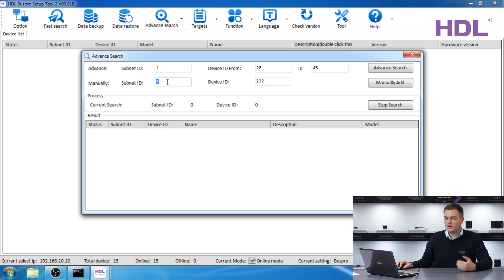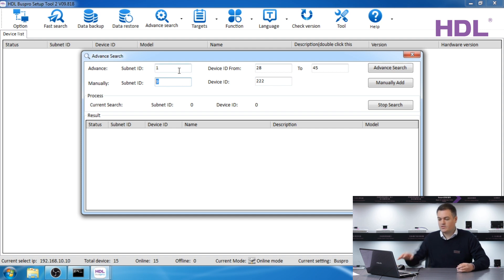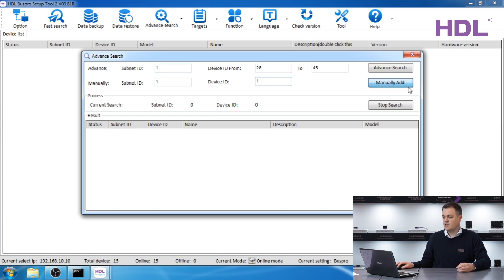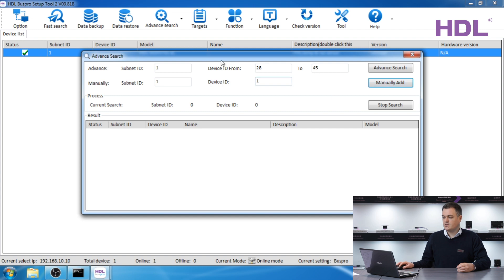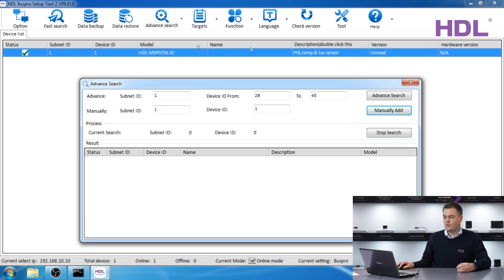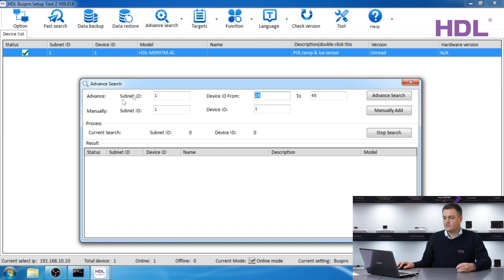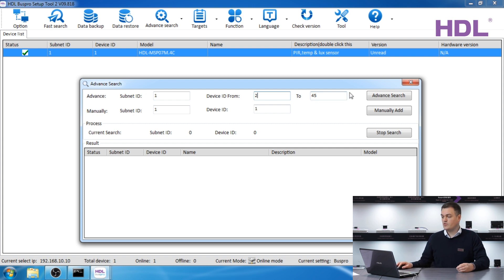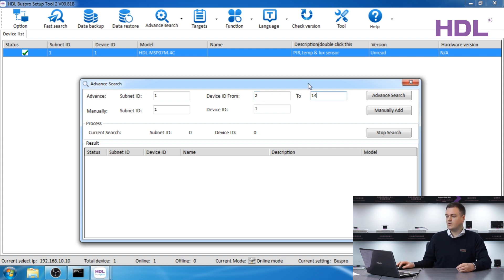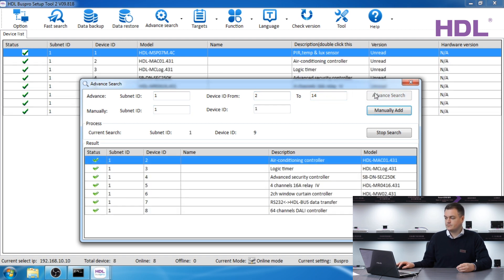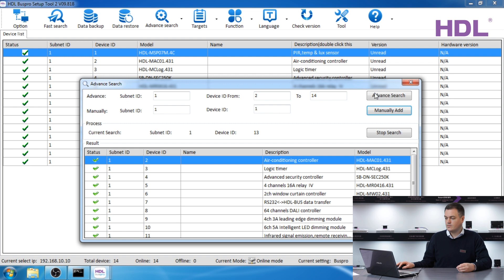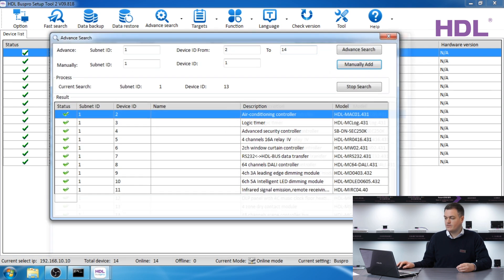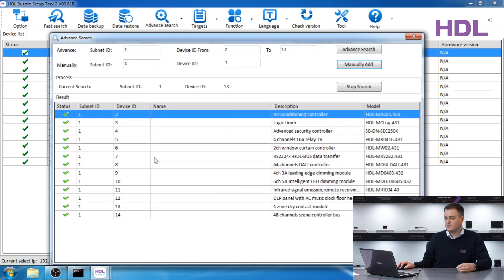So first I'll demonstrate the manual search. So if I type one and one, manually add, you can see it adds one device manually. Now let's add the other devices from the advanced search. The next ones are up from 2 up to 14, so this is the range 2 to 14 with the subnet 1. Press advanced search and all of those devices have been found. And now we can close the window.